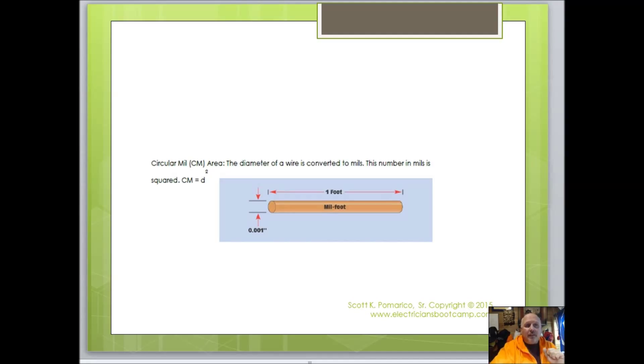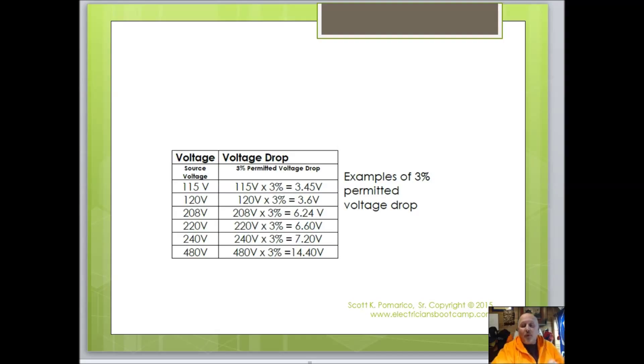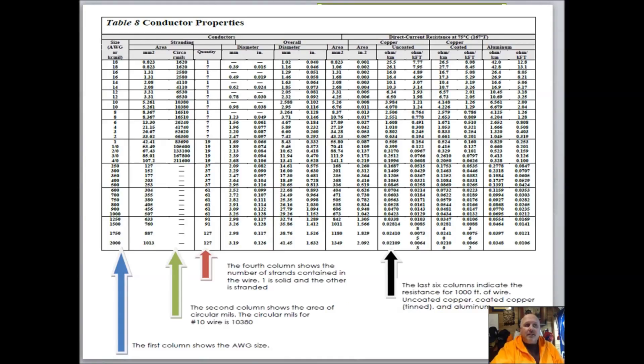The circular mill area — the diameter of a wire — is converted into mils. This number in mils is diameter squared. I've put together a table showing what voltage drop is: it's three percent of a voltage. So 208 times three percent equals 6.24; 480 times three percent equals 14.40. Those are the numbers we're looking at when talking about voltage drop. We also need to look at conductor properties.